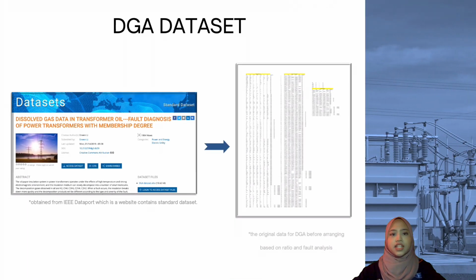The DGA dataset was obtained from IEEE Dataport, a website that contains various standard datasets. The one used in this study project is dissolved gas data in transformer oil fault diagnosis of power transformers with membership degree. In this data, there are complete datasets for all types of faults and key gases of existing gas to determine the fault of the transformer. Based on this dataset, it was arranged based on 4 different methods.